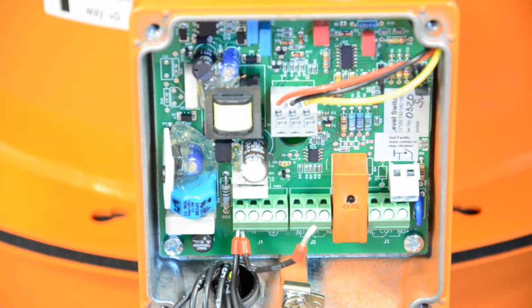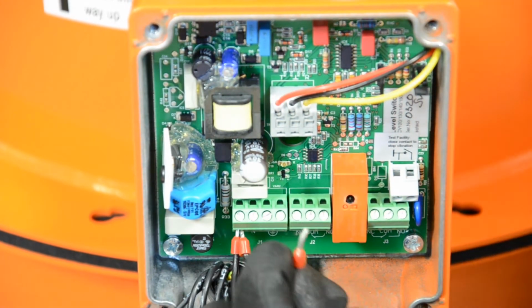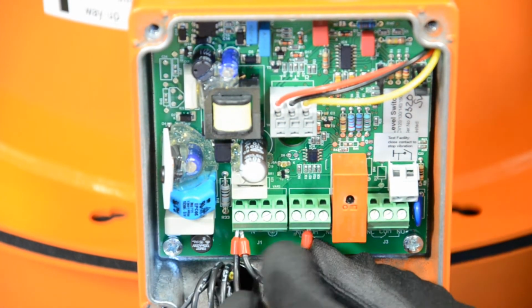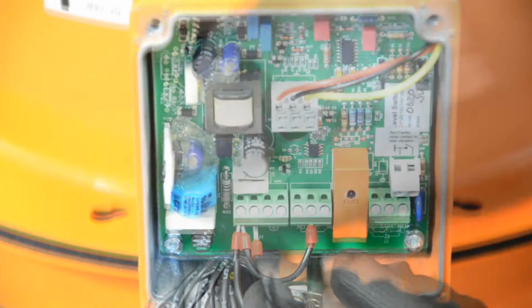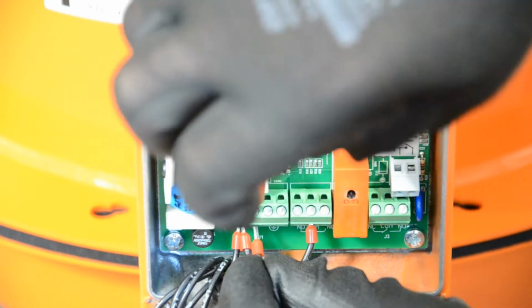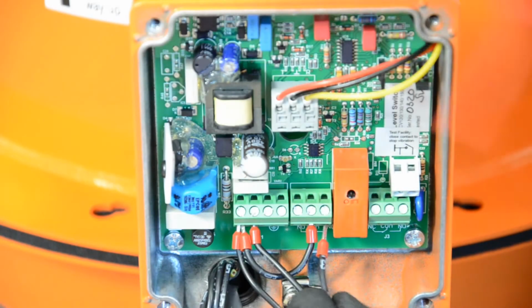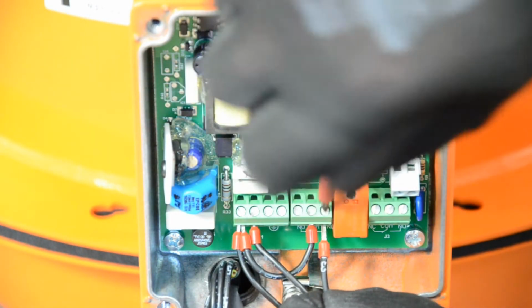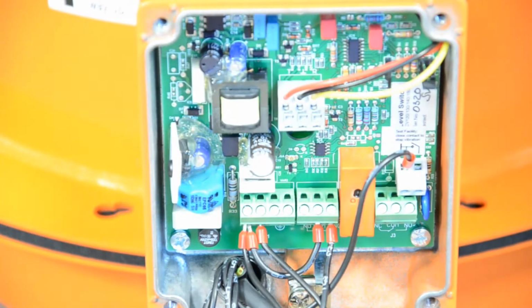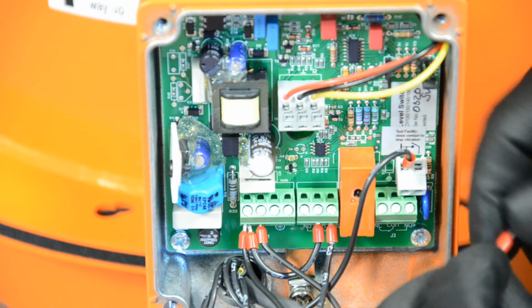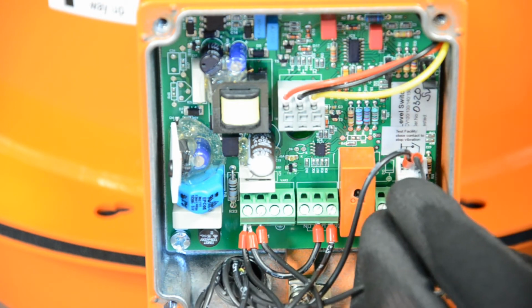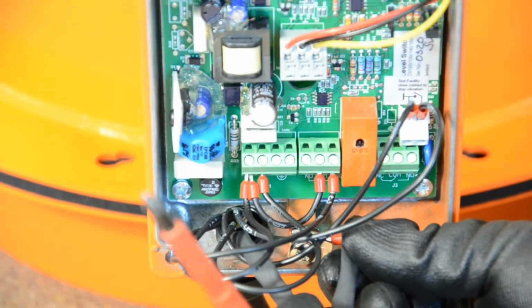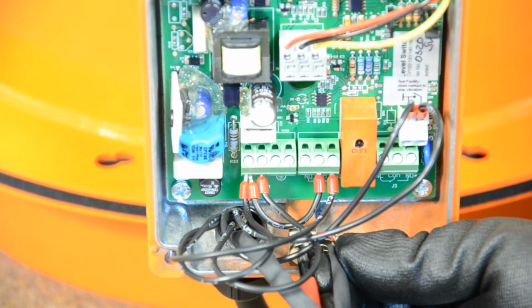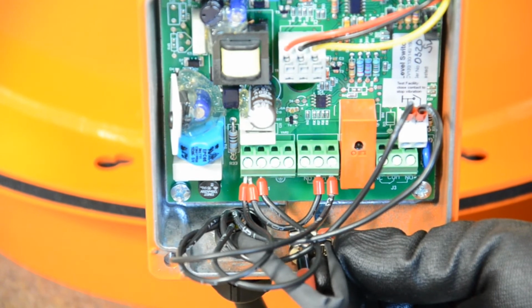Wire the supply. Terminal 1 is plus 24 volts with a link wire from terminal 1 to the common. Then wire terminal 2, which is 0 volts. Then the switch wire, number 3, connects to NC normally closed next to the link. Wires 4 and 5 are the ground level test. 4 goes to the left-hand GLT terminal and number 5 to the right. Connect the electrical shielding cable to the earth point. This only needs to be done on the probe.